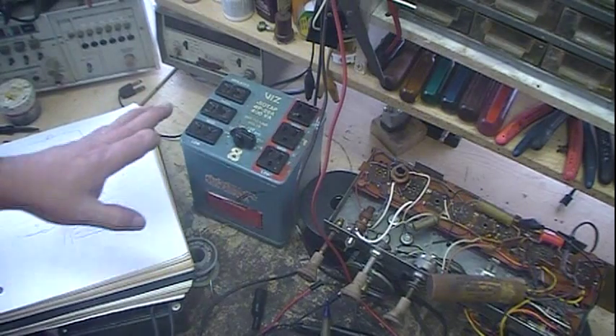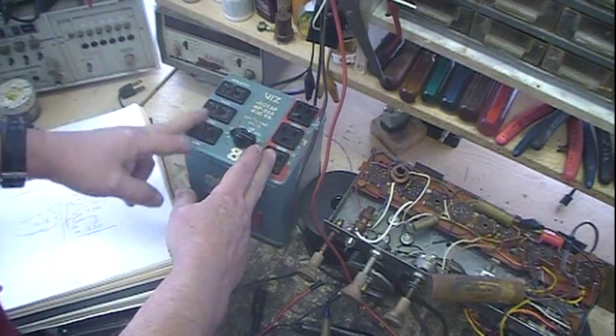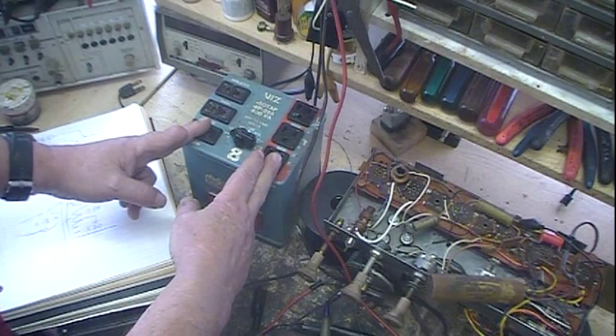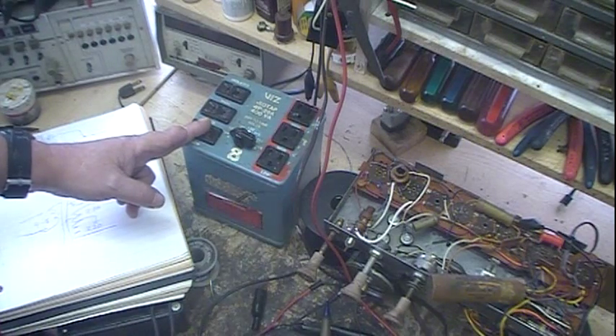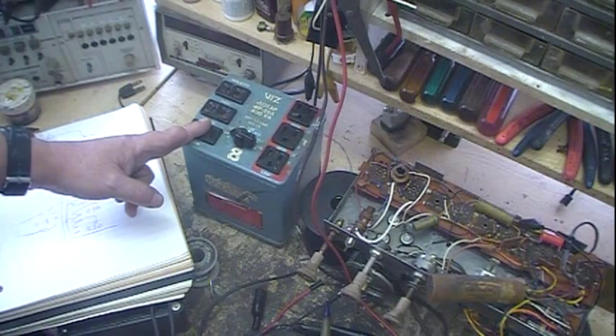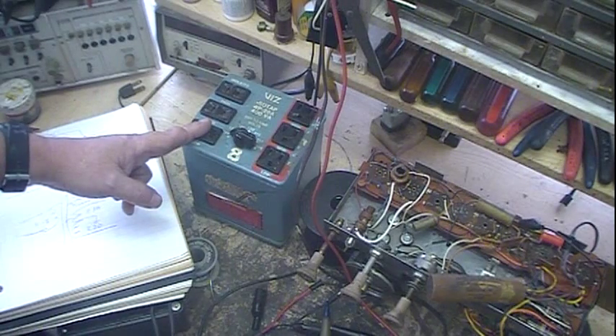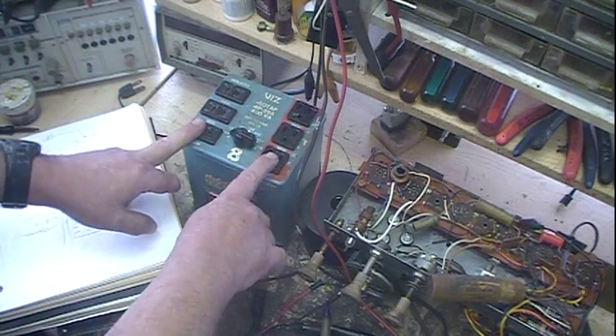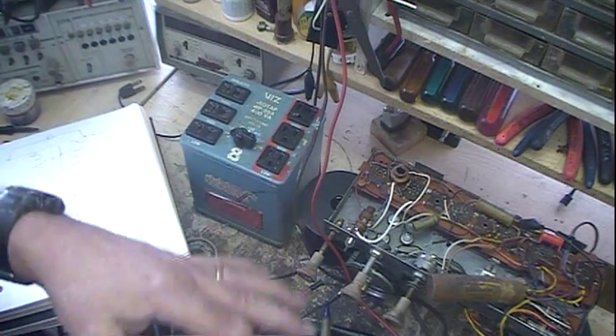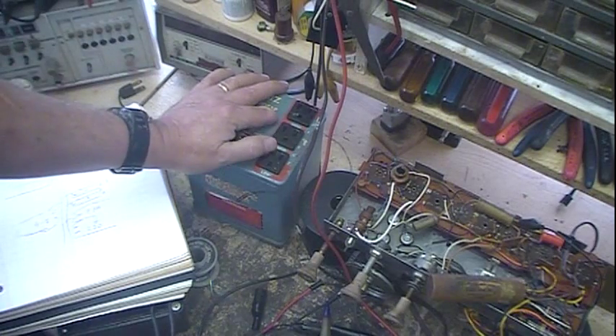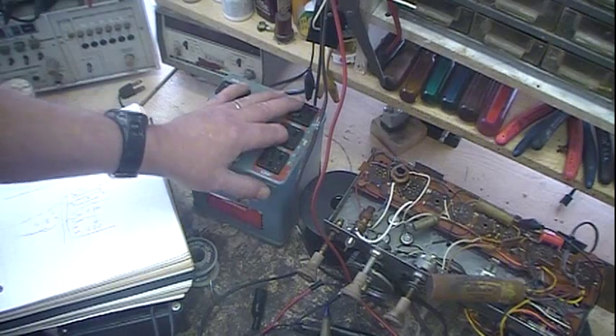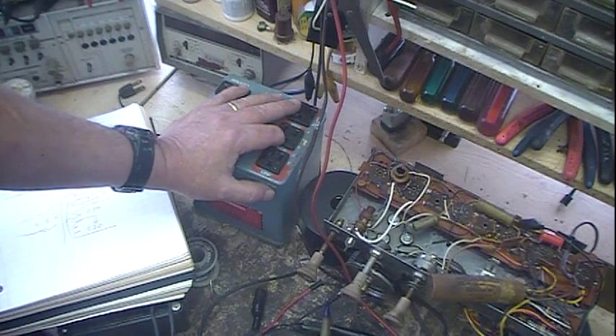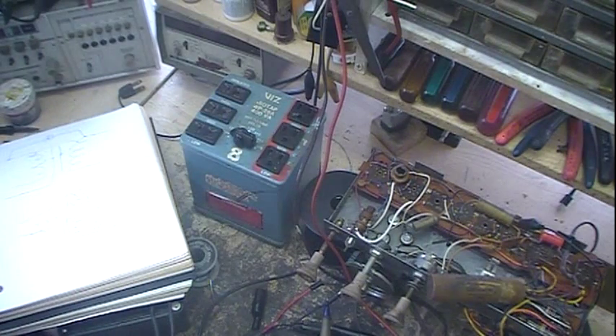So use the ohmmeter to test the isolation transformer from one side of the transformer to the other side, and as long as it's reading out of limits, which on most digital meters is OL, meaning it's outside the limits of the meter's ability to read. In a case like this, I think this meter can read up to a few tens of megohms, like 10 or 20 megohms or so. It's beyond that scale, which means basically it's not shorted. If it was shorted, it would read somewhere from the winding resistance down.